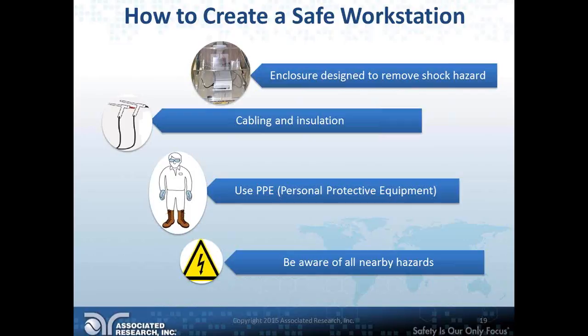You can use an enclosure. The enclosure is designed to completely remove a shock hazard because it completely cuts off hazardous voltage. You can't reach within an enclosure while testing. You might have some interlocking device in there, so if that door opens, the test immediately stops. An enclosure, in my opinion, is one of the absolute best ways you can get around any type of shock hazard because the user can't even touch it while the circuit's energized. That's my personal favorite method. I use enclosures in my lab all the time—I have several of them that I employ on a regular basis when I'm doing testing.